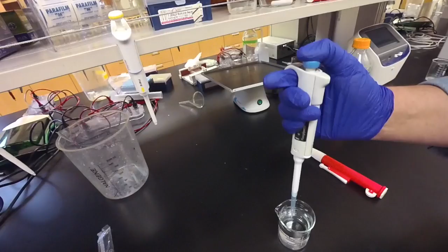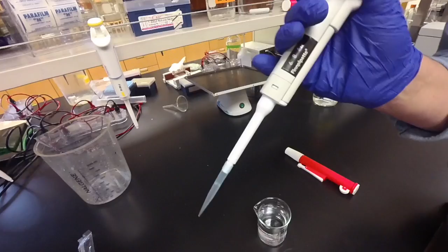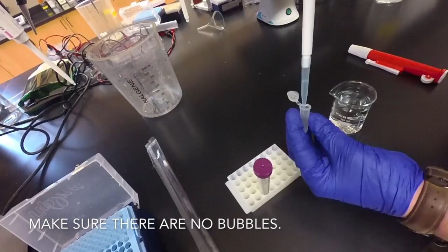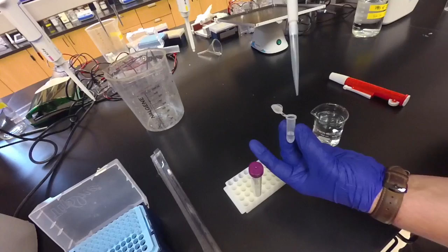When picking up liquids, insert your pipette into the liquid, press it down to the first stop, release, and pull out of the liquid. You've now just picked up 685 microliters of liquid. Now, go over to wherever you're going to place this. In this case, I'm going to put this into a 2 milliliter centrifuge tube. Press it down all the way to that second stop that I showed you earlier. Pull out the pipette tip before releasing.